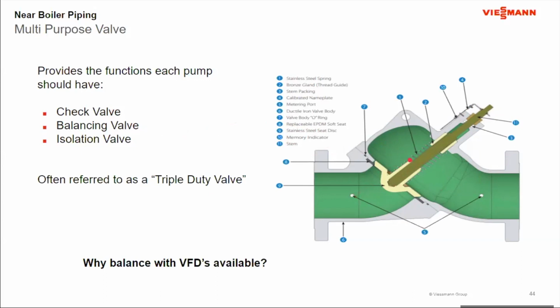So I can use this to set the flow from a balancing standpoint to get the proper flow through the pump. And if the end of the shaft is right here, because I balanced it, when the pump starts off, the spring holds the seat in place until the pump pushes, and then the pump will push the seat up until it contacts the stem, and at that point it's balancing. So that gives me my balancing function and check function in a single seated device.